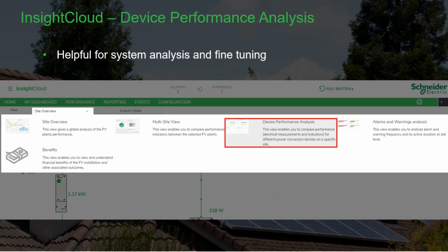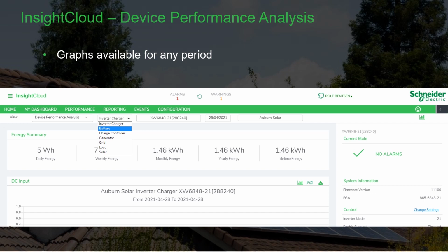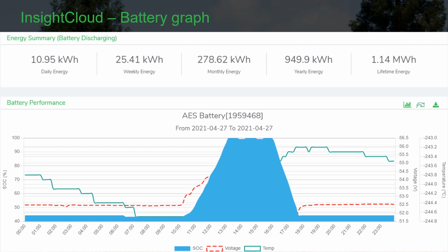Device performance analysis allows the installer to see trends at the device level. This is important when you need to determine how much stored energy is being used and when. For example, if I want to see the depth of discharge of the battery on a daily basis, I can select the battery monitor from the device list. Here you can see the storage utilization on a given day. You can make changes to device settings through the cloud. This is an extremely valuable tool for installers to have available to them, especially for time of use.